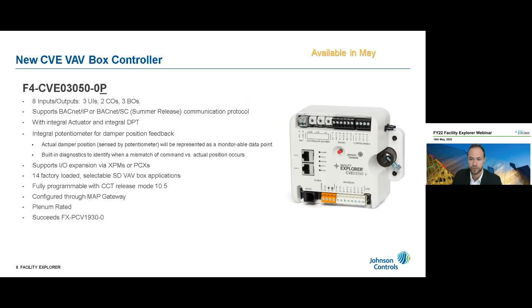So this is a sample of the 14 preloaded applications. They support most common types of VAV applications. So supporting logic, accommodating the NS8000 sensors, and they utilize the CO2 sensors, if present, for minimum flow reset, and inclusion of a discharge air temperature sensor in cooling only applications. These apps are currently built in Imperial units, and soon we'll be releasing support for the metric units.